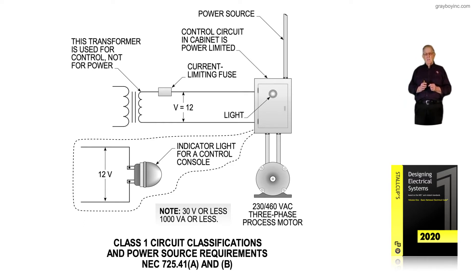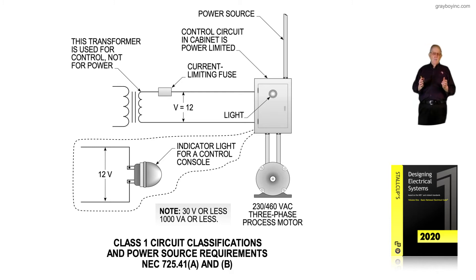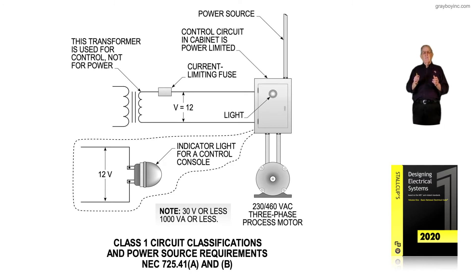NEC 725.41B deals with power-limited circuits. That section states that a Class 1 power-limited circuit is 1,000 volt-amps or less, and usually 30 volts or less. This gives us the classification of a power-limited circuit versus a non-power-limited circuit.